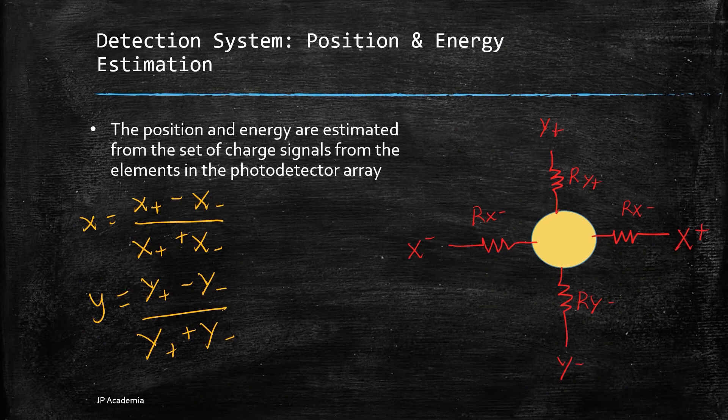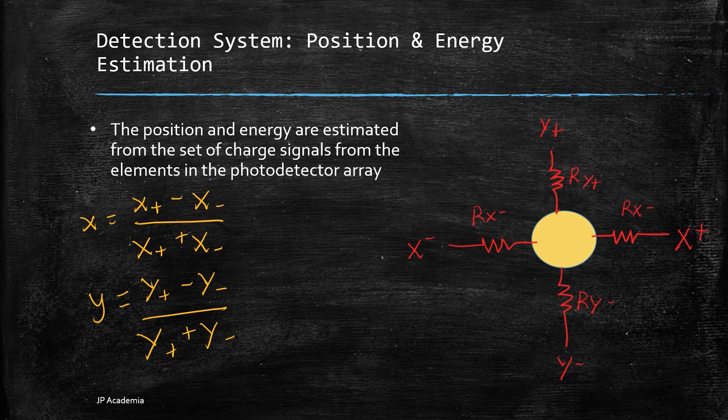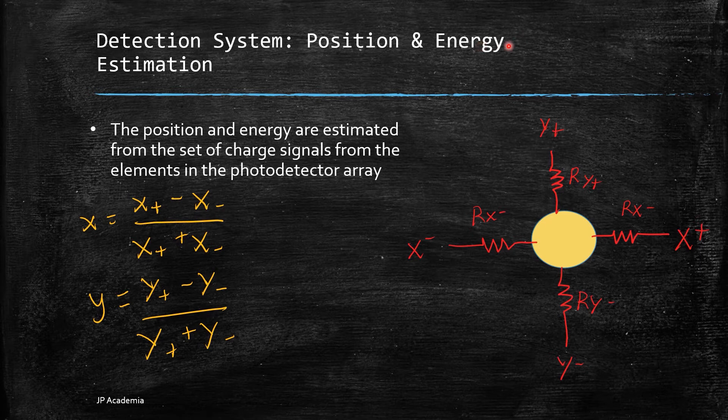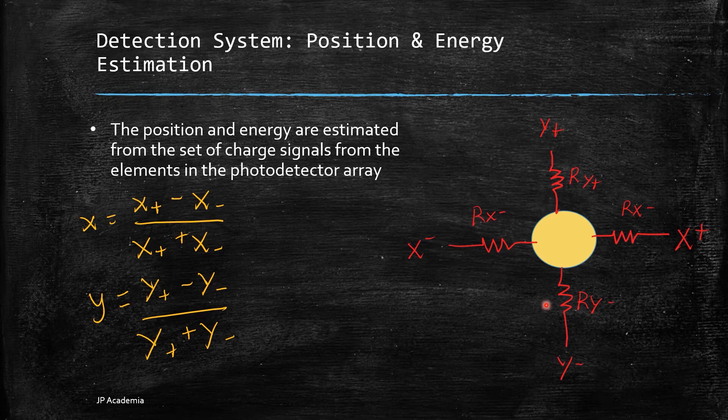Now let's talk about position and energy estimation in the detection system of gamma camera. The goal of the radiation detector is to provide an estimate of the energy and interaction position of each gamma ray incident on the detector. We have this resistive network used to implement the position estimation. Let's say we have a single photomultiplier tube here, PMT.